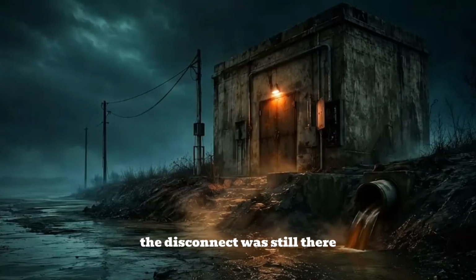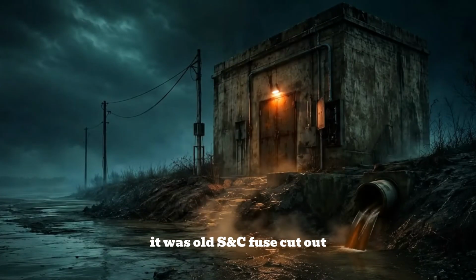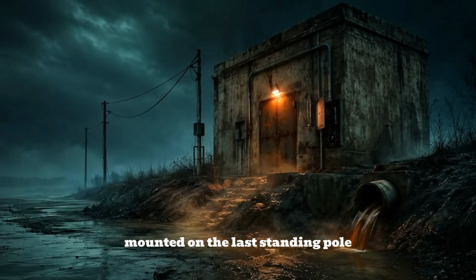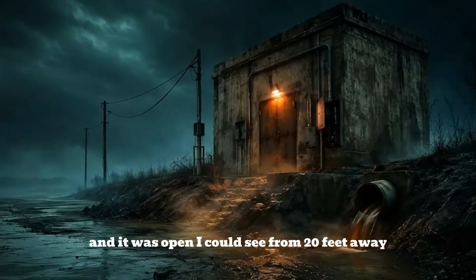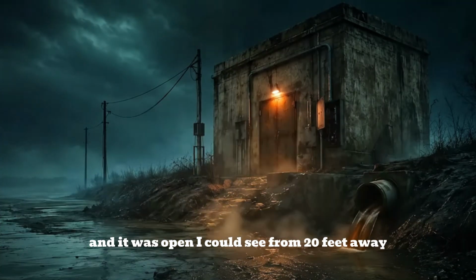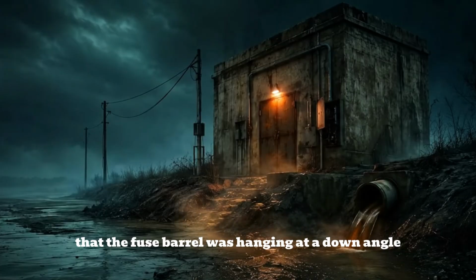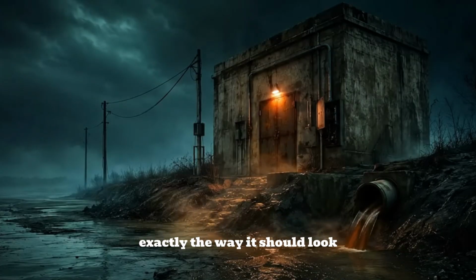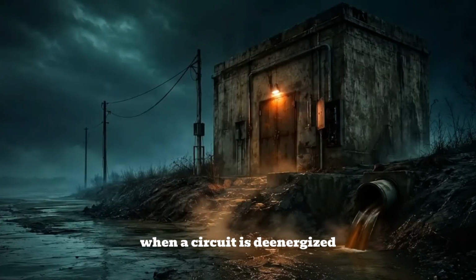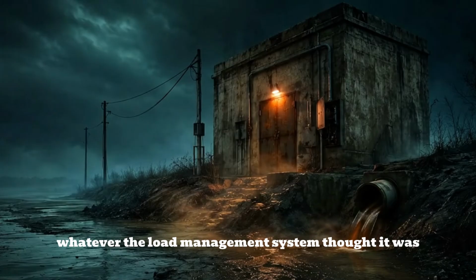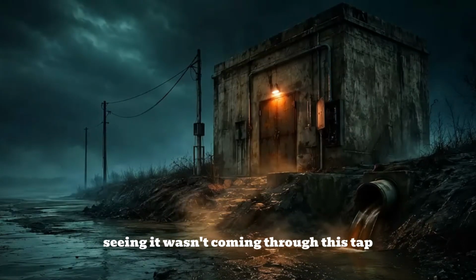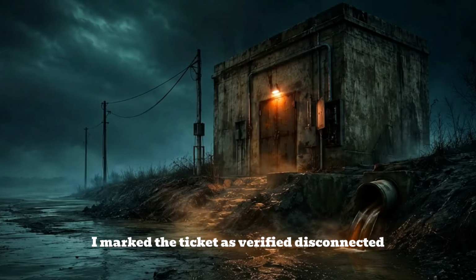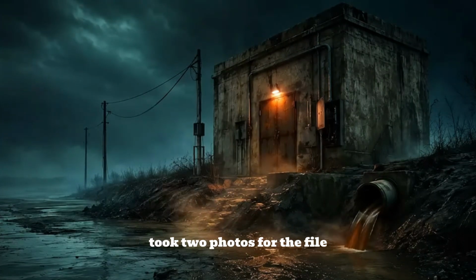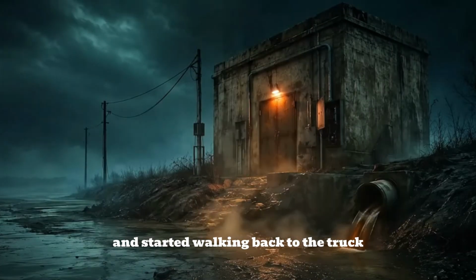The disconnect was still there. It was an old S&C fuse cutout mounted on the last standing pole, and it was open. I could see from 20 feet away that the fuse barrel was hanging at a down angle, exactly the way it should look when a circuit is de-energized. No connection, no path for current. Whatever the load management system thought it was seeing, it wasn't coming through this tap. I marked the ticket as verified, disconnected, took 2 photos for the file, and started walking back to the truck.